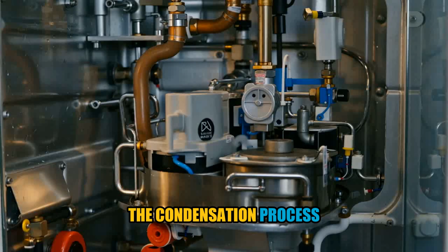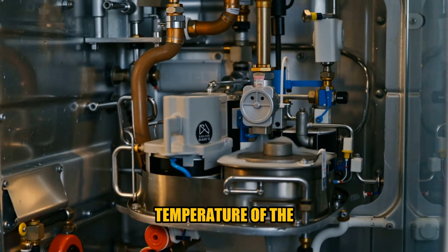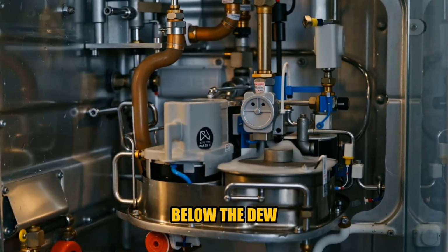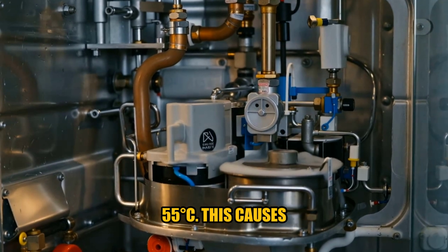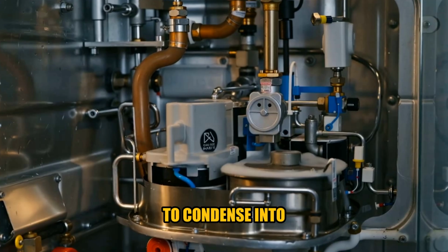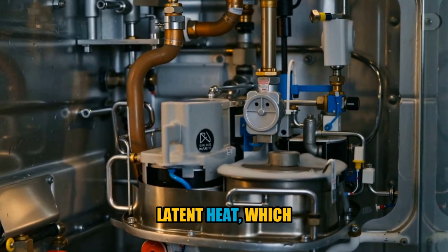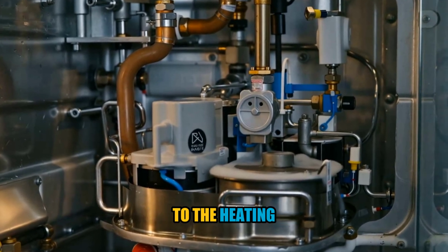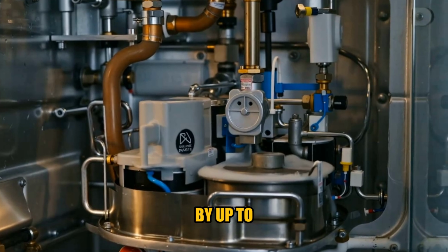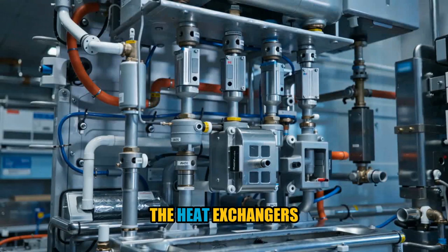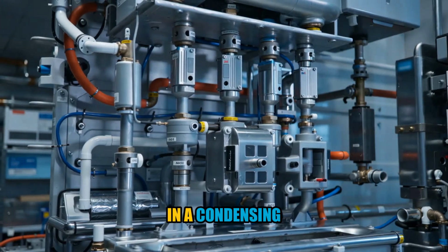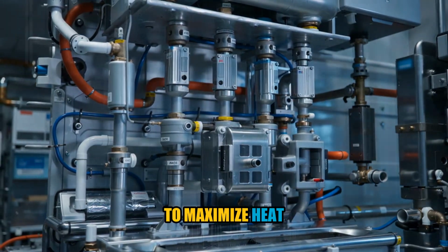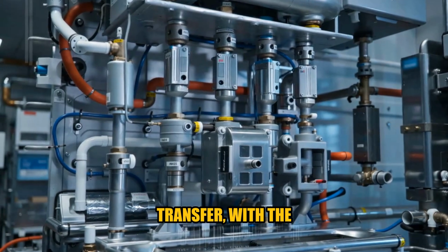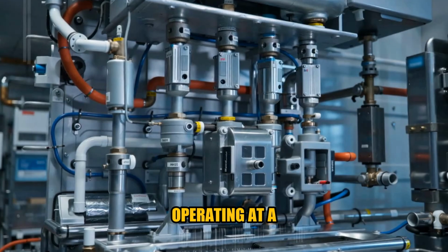total heat transfer. The condensation process occurs when the temperature of the flue gases drops below the dew point, typically around 55 °C. This causes the water vapor to condense into liquid water, releasing latent heat, which is then transferred to the heating system, increasing efficiency by up to 12%. Heat exchangers in a condensing boiler are designed to maximize heat transfer, with the primary heat exchanger operating at a temperature of around 80 °C.